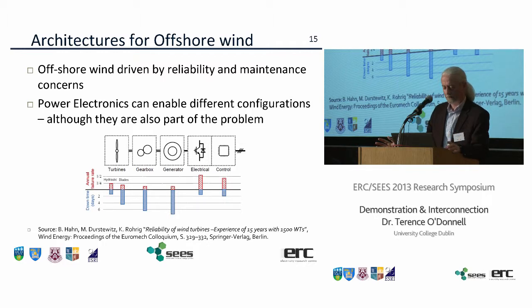This graphic shows a collection of reliability data taken from 1,500 wind turbines over 15 years. It shows the annual failure rate of various parts of the wind turbines on top, and the number of down days attributable to those on the bottom. You can see that electrical components have the highest annual failure rate, but they actually contribute to the smallest downtime. So the power electronics, although they fail often, are relatively easy to replace—but they still raise reliability concerns.